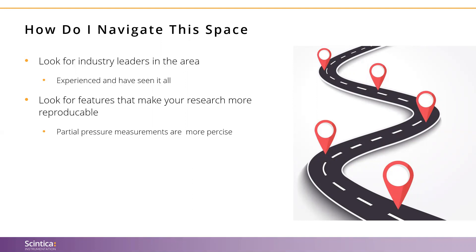More focused on individual products: look for features that are going to make your research more reproducible. Just choosing to work under physiologically relevant conditions is an excellent step. But to take this one step further, it is worth looking into systems that take measurements using partial pressures as opposed to percentages, as partial pressures are more precise day to day and location to location because they account for changes in atmospheric conditions. For example, if a large storm rolled in that changed barometric pressure by 5%, cells in a system reading percentage would be off by 5%, but cells using partial pressure would remain at the exact same oxygen condition.